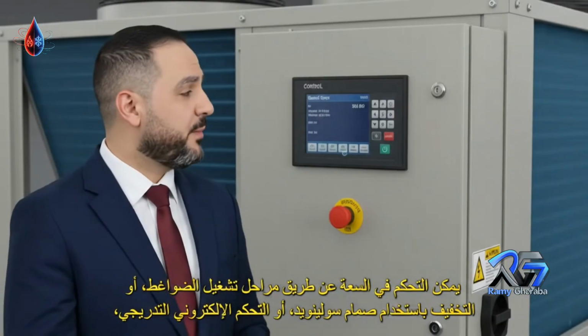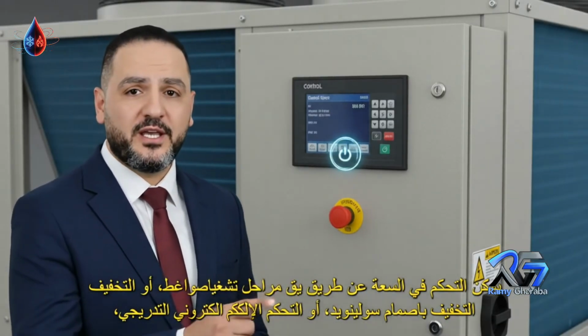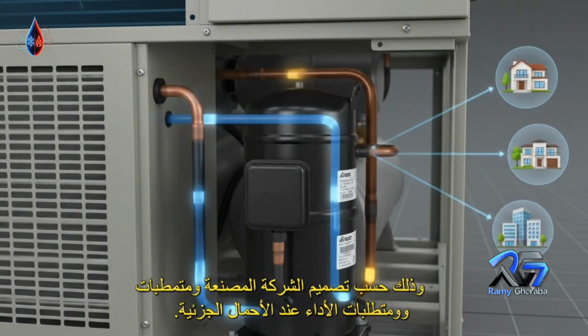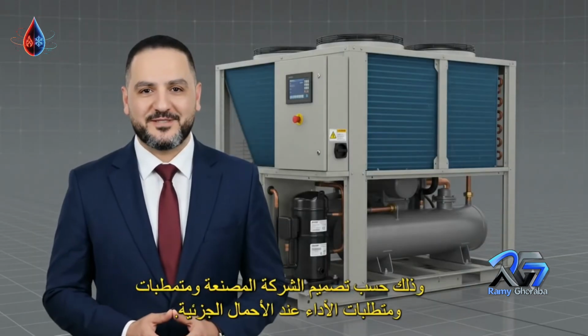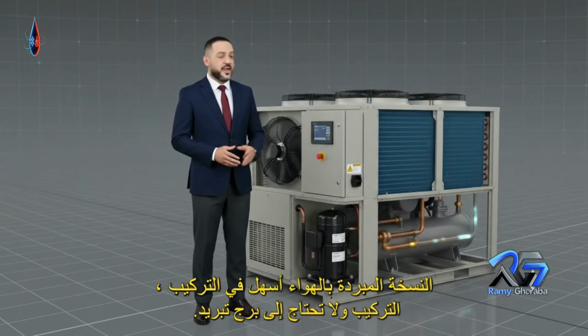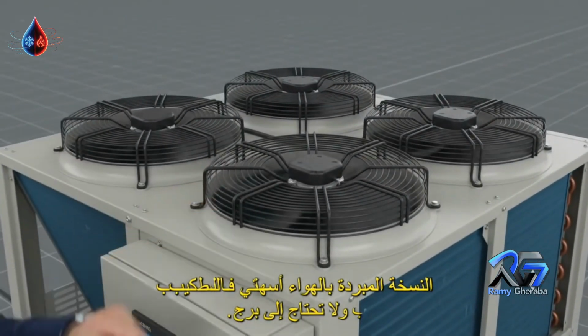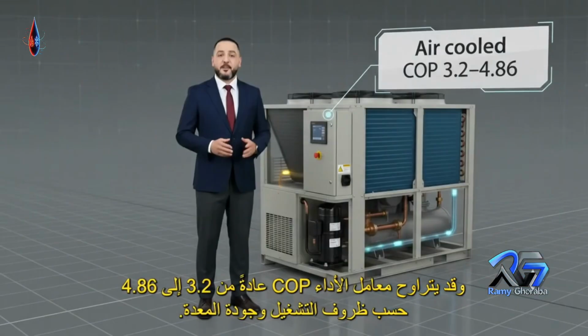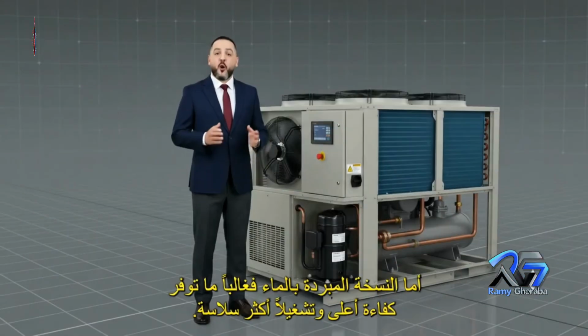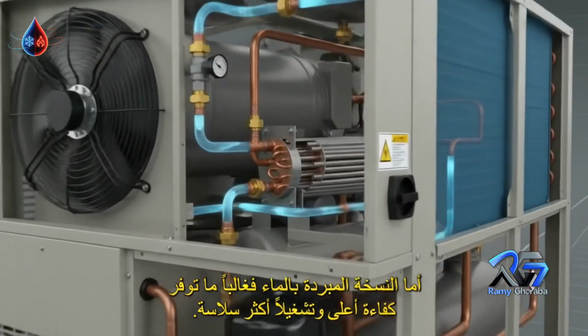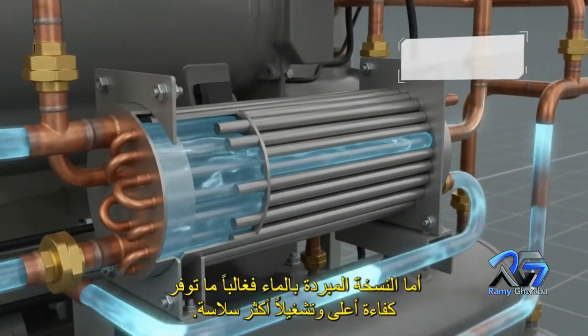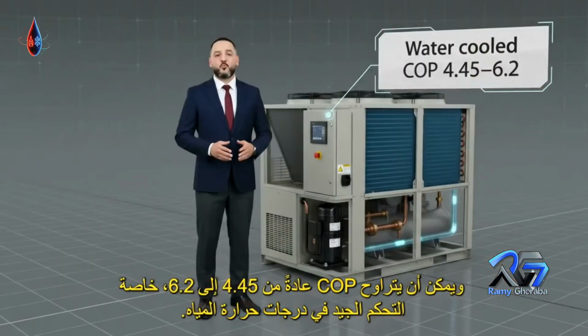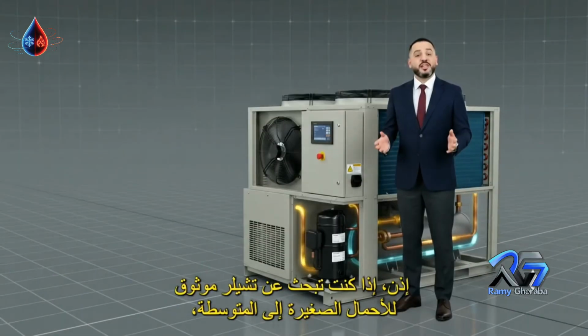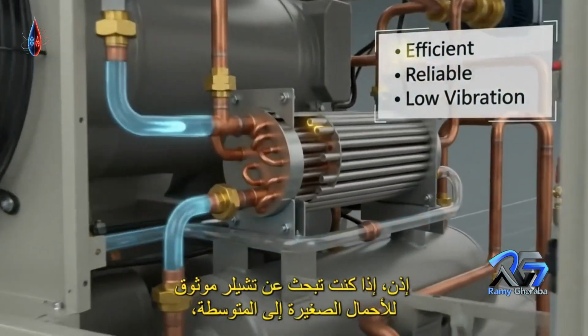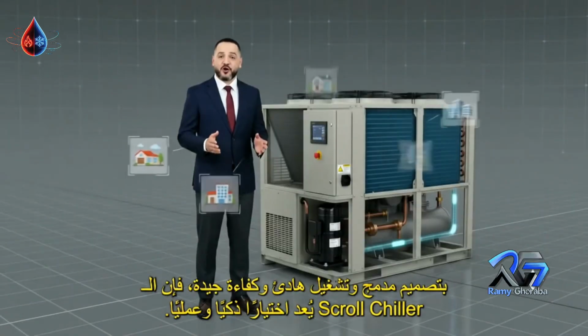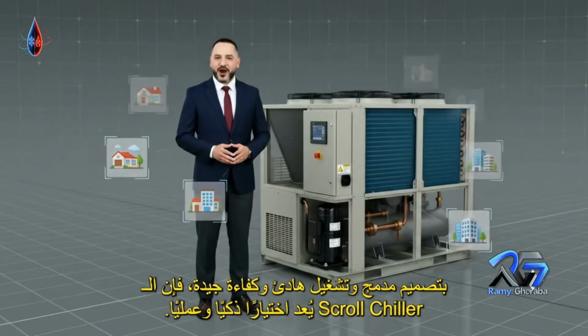Capacity control may be achieved by compressor staging, solenoid-based unloading, and electronic modulation, depending on the manufacturer's design and the required part load performance. The air-cooled version is easier to install and does not require a cooling tower. Typical COP values may range around 3.2 to 4.86, depending on operating conditions and equipment quality. The water-cooled version usually offers higher efficiency and smoother operation. Its COP can typically range from about 4.45 to 6.2, especially when water temperatures are well controlled. So, if you need a reliable chiller for small to medium loads with compact design, quiet operation, and strong efficiency, the scroll chiller is a smart and practical choice.